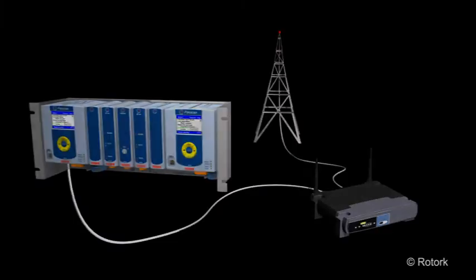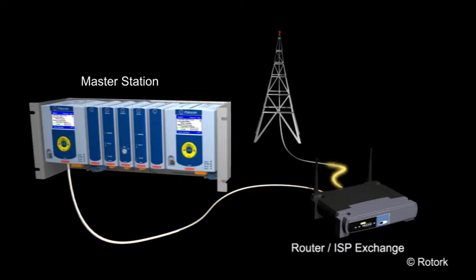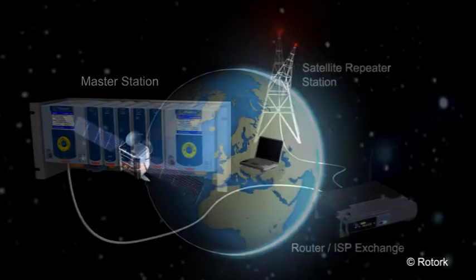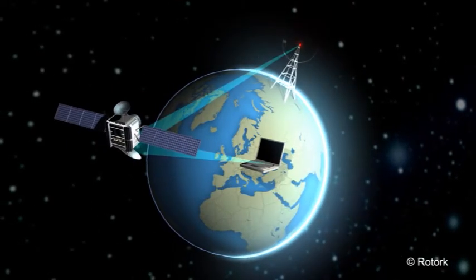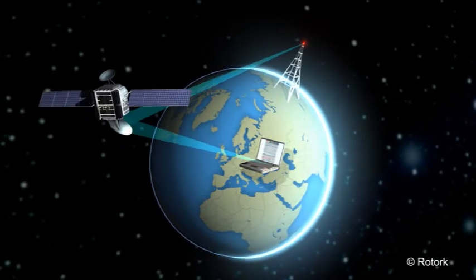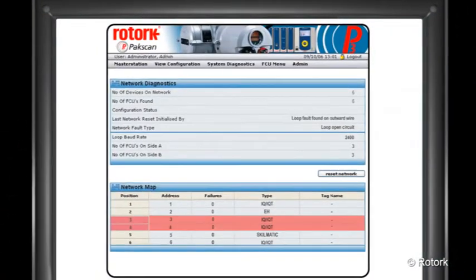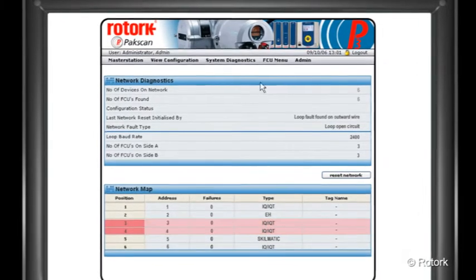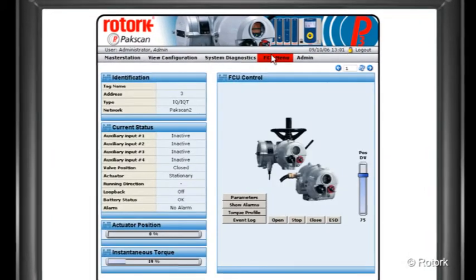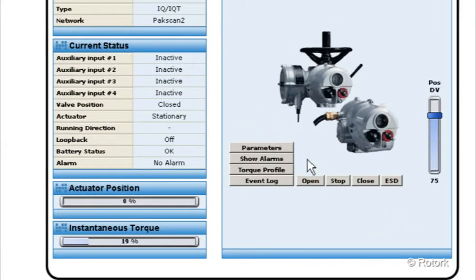The data gathered from each actuator by the master station is made locally available via multiple serial and Ethernet ports, and can also be accessed in any global location using standard Ethernet infrastructure. This means that from any location, individual actuators can be securely interrogated using the master station's built-in web pages.